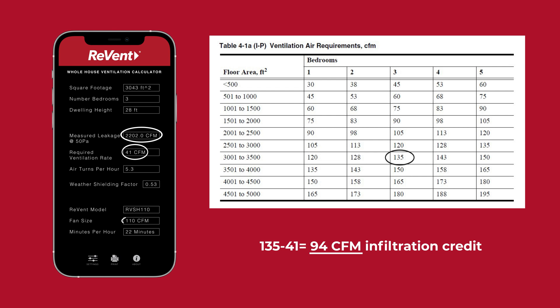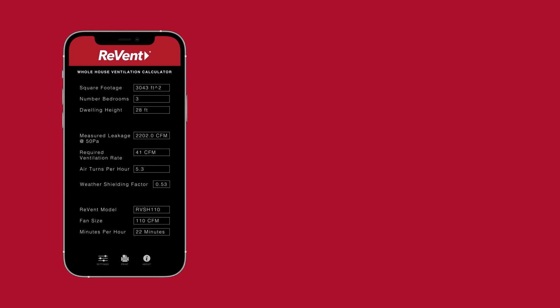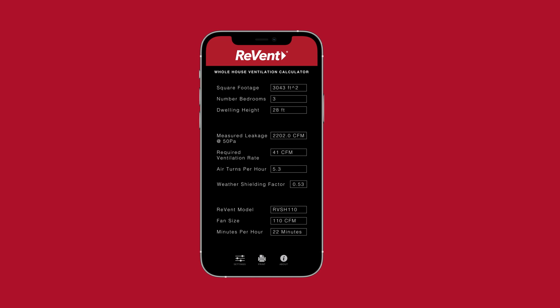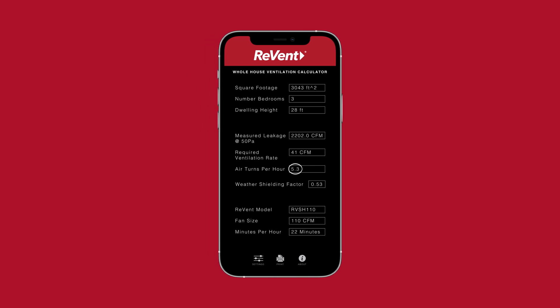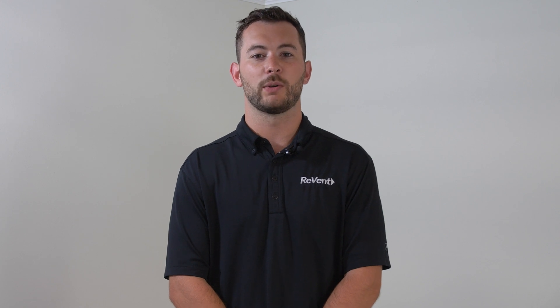We set the home's 110 CFM Revent fan to run 22 minutes every hour, which meets the ventilation requirement. The app also calculated that this home produces 5.3 air turns per hour. On this particular house, we are required to have 5 or less air turns per hour. With some minor adjustments, the builder can tighten the home to meet the requirements.